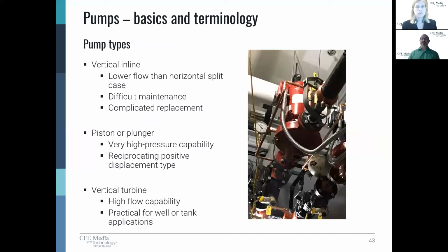A vertical inline is great because I can fit it in all kinds of compact spaces, but then somebody has to get to it again. And they can be fairly heavy. If you're going to specify vertical inline pumps, make sure that somebody has a plan for how they're physically going to get to it. If they're smaller and somebody can hold it with one hand on a ladder, then that's probably fine. But if they're going to be larger, keep in mind that if you put a 50-pound pump 10, 15 feet in the air and surrounded by pipes, you're going to give someone a hard time when they go to service it or replace it in the future. And as you're looking at all the various types, whether it's vertical turbine or piston or plunger, each one has a very specific application for which it's designed.